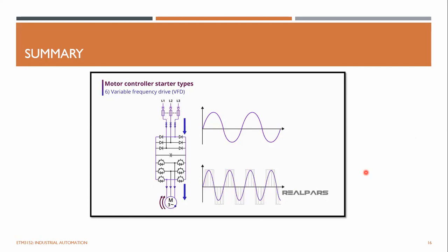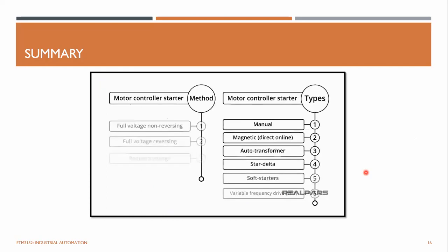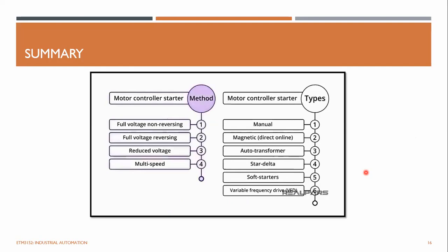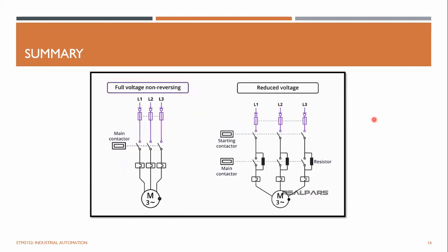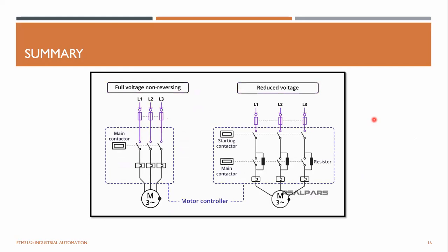VFD. This video has provided a brief overview of 4 types of motor controller starting techniques and 6 types of motor starting devices. Whether a full voltage across-the-line motor controller is required, or a motor controller to provide a reduced voltage at startup, there is a motor controller that allows safe, efficient, and controlled starting for every application type.